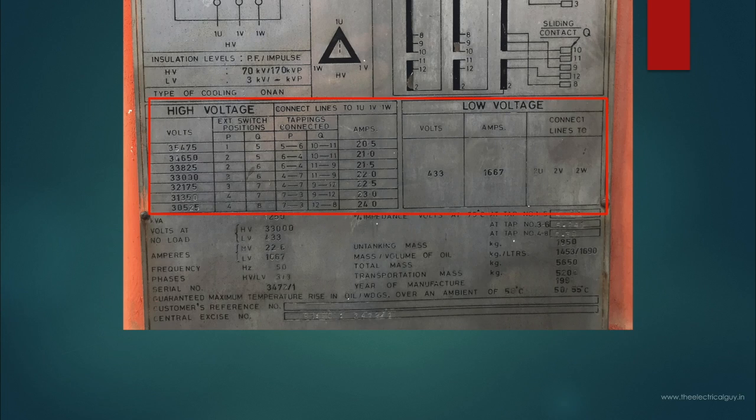Moving on here you can see the details of taps which are provided on the high voltage winding are given. In case if your high voltage is fluctuating then accordingly you can adjust the taps and get the constant output at secondary that is 433 volts. This detail shows the connections where you have to connect your tapping to get the constant voltage and also gives you the amperes based on the connection at high voltage.